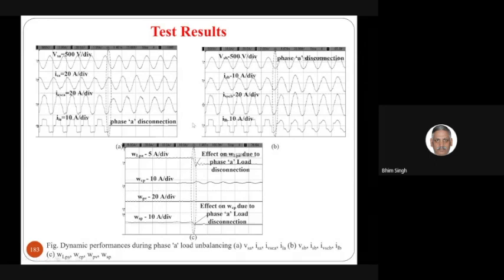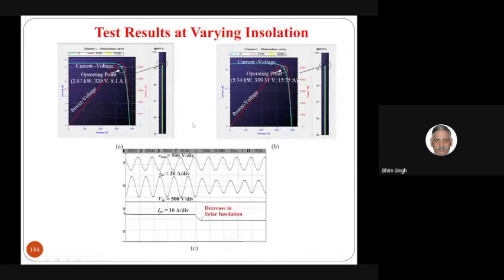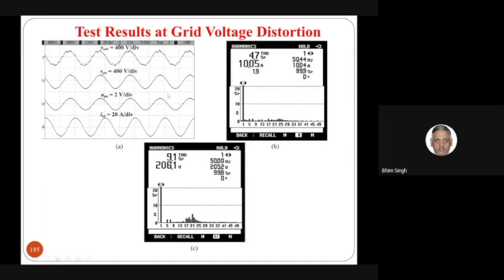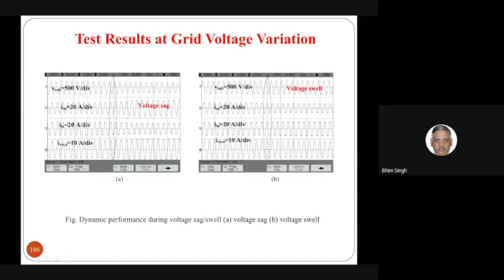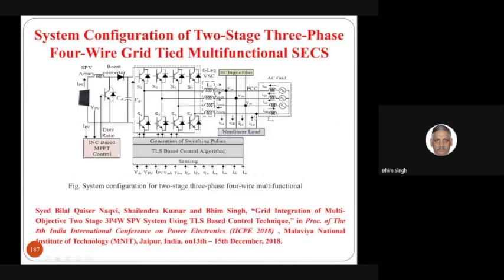Similarly, when solar generation changes, accordingly the solar generation is less, so less current is reduced on the grid side. When voltages are distorted, we have extracted the fundamental voltage without distortion, and even with a voltage THD of 9.1%, the current THD is only 4.7% or so. And when there is a grid voltage variation, you have voltage sag and voltage swell, it does not really affect it. The power variation is there, but the current remains sinusoidal and balanced, also at unity power factor.